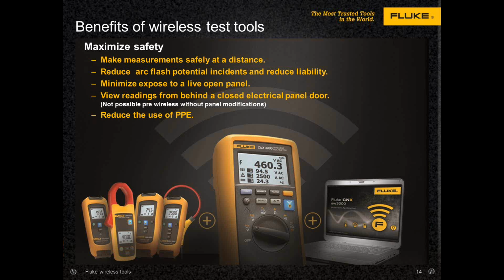The wireless tools allow you to hook up to that panel with alligator clips to whatever you want to measure. If this panel is live, you're going to be in PPE. If it's not live, you can install these modules without PPE, put the panel covers back on, close it up, and then fire it up with the panel cover in place.